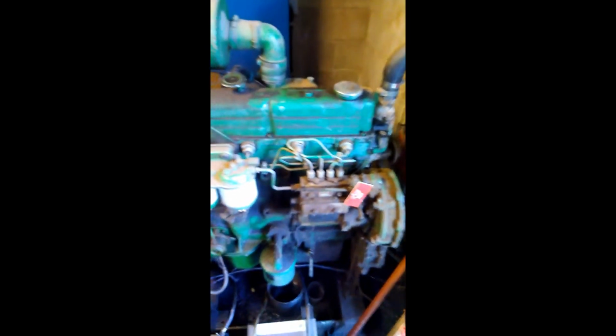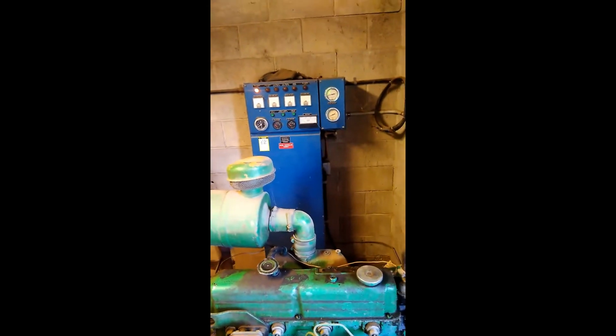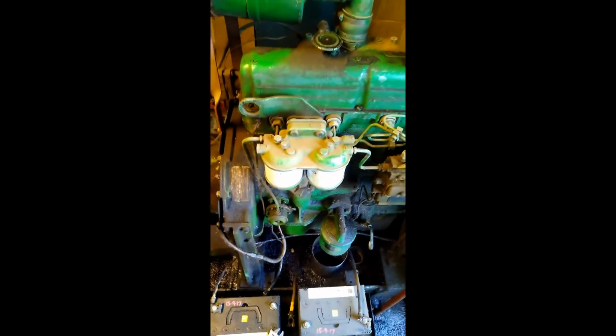Then you go back over to the door, and above the door is the electric pump isolate switch. That'll stop the electric pump from starting up, and the diesel pump, the controller doesn't isolate it, so you have to take the positive sides off the battery and just drop them over. So that's the diesel isolated and the electric isolated and the sprinkler system isolated.